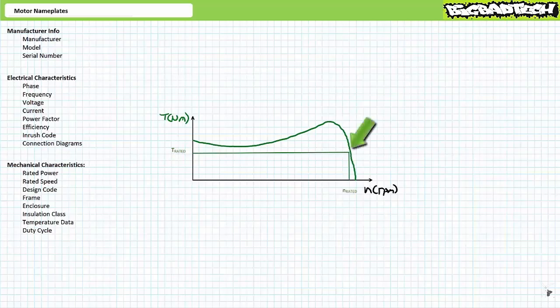Again, the rated condition is a single point inside a larger operational range. The entries in a motor nameplate assume this rated condition. What's nice about this fact is customarily motors are operated at or around the rated condition because that is what the motor has been specifically designed to do. Why would you regularly overload a cheaper 3/4 horsepower motor with a larger 1 horsepower task? The 3/4 horsepower motor won't be as efficient and most likely won't survive repeated use.